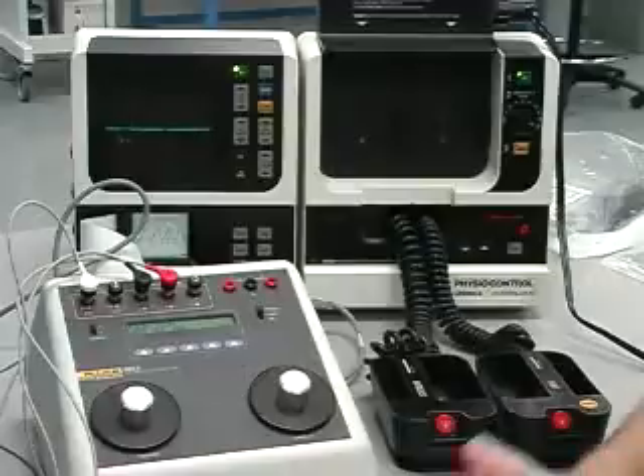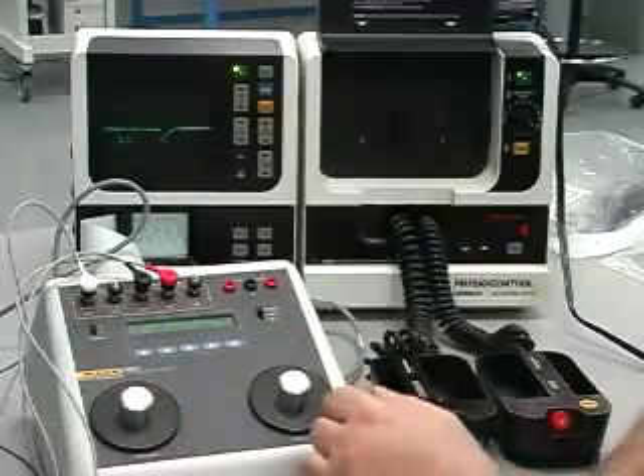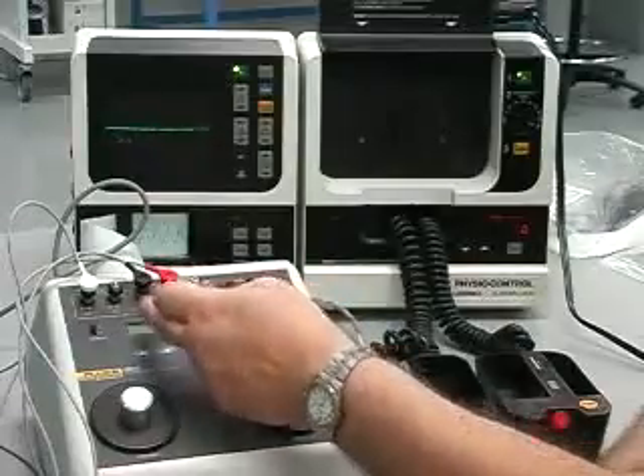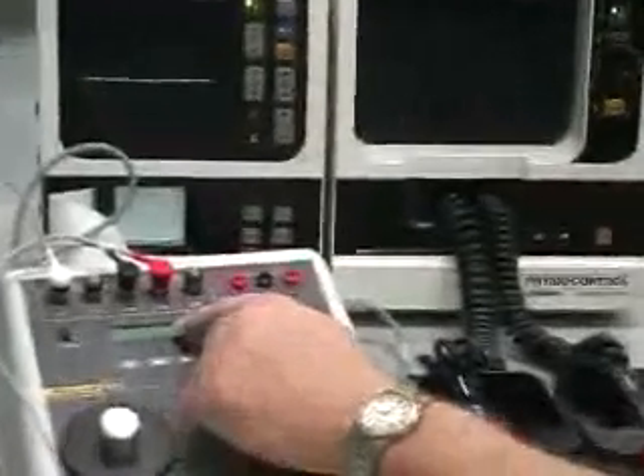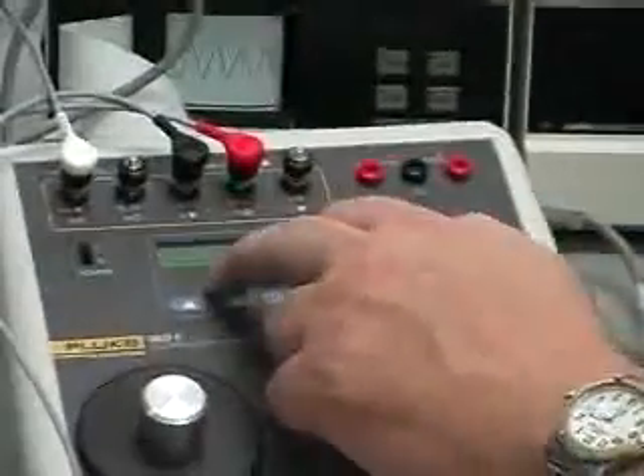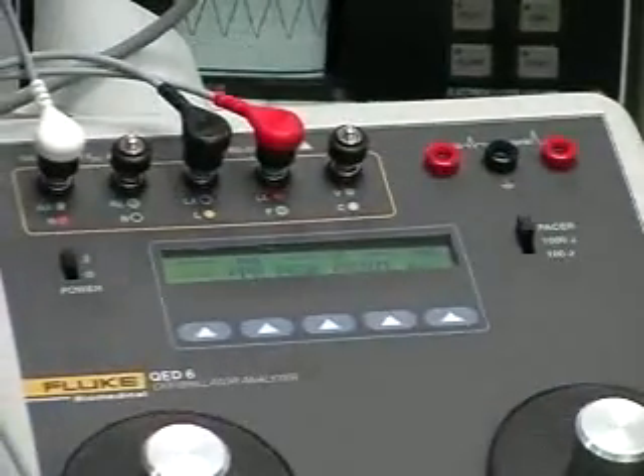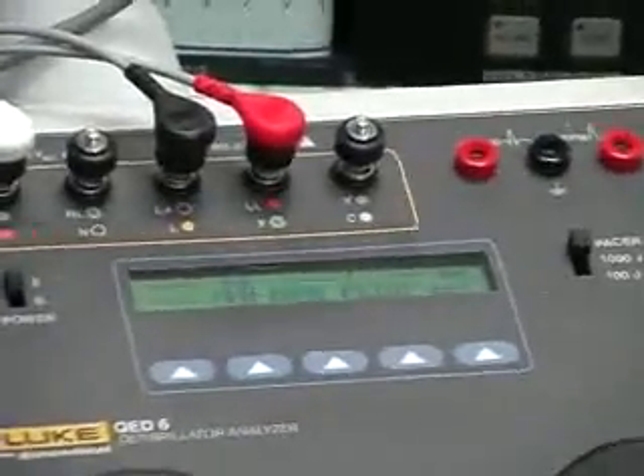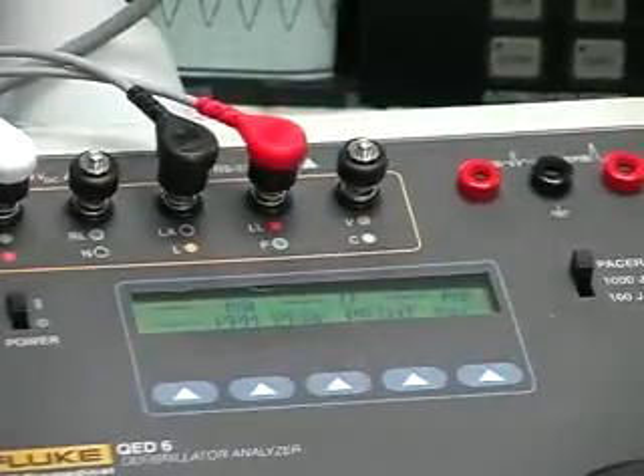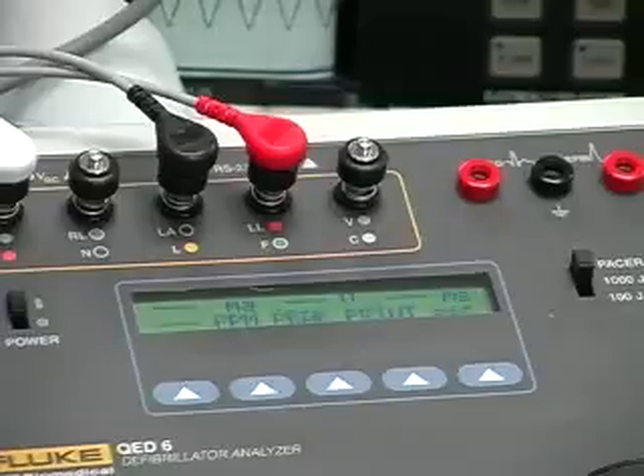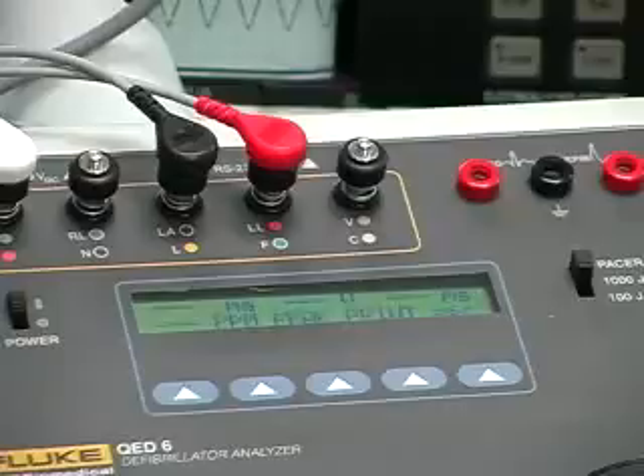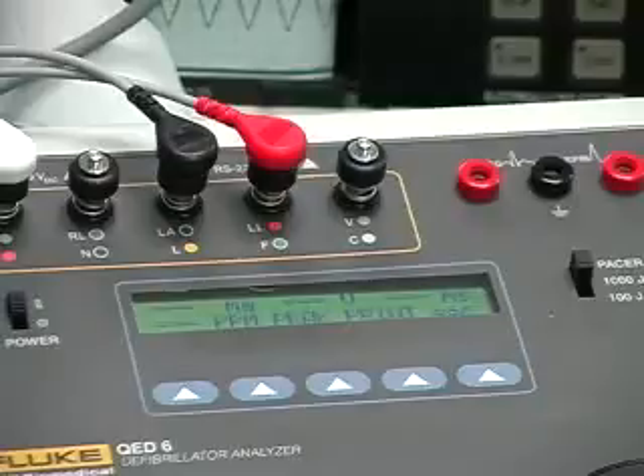Okay, quickly for the pacer, you have the ability to measure it. It shows the current level, the output amplitude, the voltage peak, the width in milliseconds, and the rate of the pacer. There are also tests for refractory period, looking at the ability of the pacer to interact with a patient whose ECG is intermittent, or occurs at different intervals following the pacer's waveform spikes. Again, this makes sure that if the patient has any normal ECG activity, the pacer senses it properly and doesn't output any pacer spikes at the improper times.